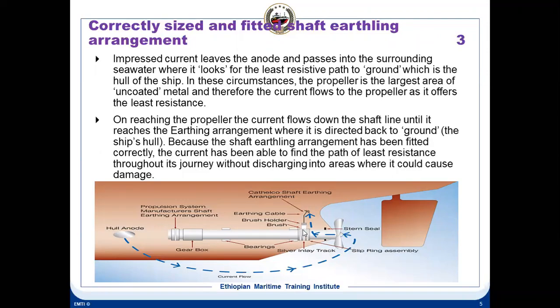So, as I told you, the shaft grounding millivolt has to be inspected daily. Millivolt means the potential between the shaft and the hull. It should be less than 80 millivolt. Whenever it exceeds, you have to clean the brushes. You have to check the grounding also. Sometimes the grounding may be improper. You will have this problem. Normally you will find two sets of brushes on both sides, and these are silver graphite brushes here.